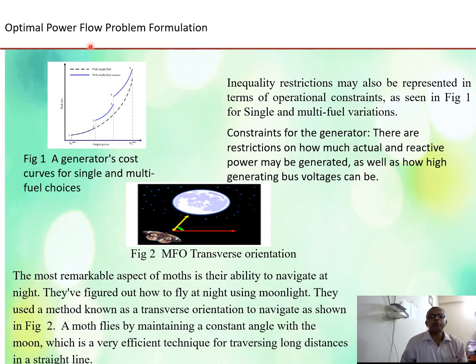Now, about the optimal power flow problem formulations. Inequality restrictions may also be represented in terms of operational constraints, as we can see here, a generator cost curves for single and multi-fuel choice. Constraints for the generators: there are restrictions on how much actual and reactive power may be generated, as well as how high the generator bus voltage can be.